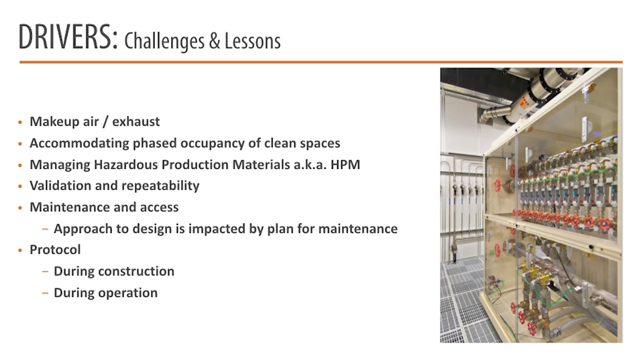On HPMs, one thing I'd say is we did a project for a client in downtown Cambridge where we were consolidating clean room operations into one suite on an upper floor. The idea was to take the hazardous gas room supporting that space and move it too. But you're limited in the volume of hazardous gases of all varieties you can store and have in use - every level you go up in a building reduces how much you can store in one place. In the end, we left the HPM room on the floor below right where it was, because we could have the quantities we needed to feed up into the clean room. If we'd moved it up, we couldn't have kept a proper quantity of HPMs up there.